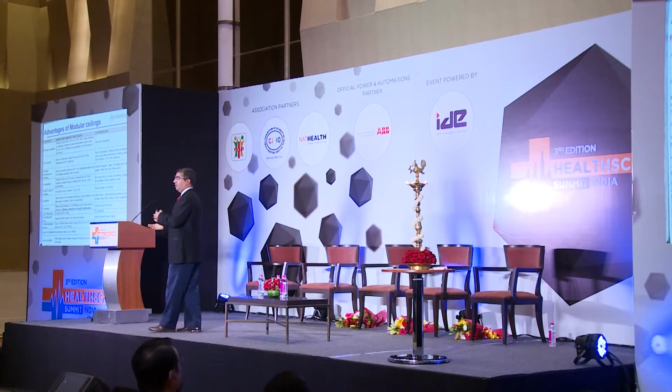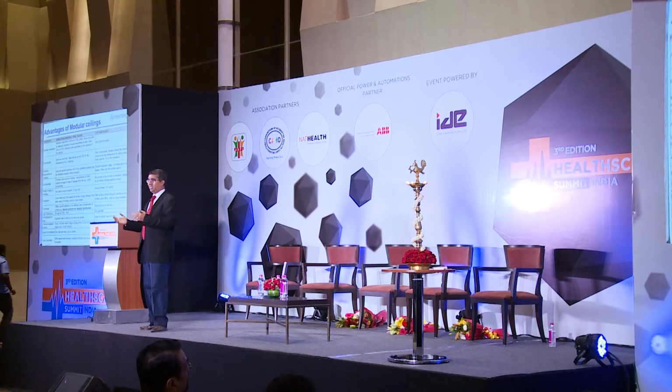And when you go for metal perforation, which is a very fatal error in most hospitals, currently also happening in India, the perforations collect dust and dirt, and if you have fleece on the backside, it becomes a backyard of bacteria and germ growth. And if a highly infectious patient comes in, that room is a fatal room for the next patient. In a way, if you don't use a different AHU where you're using perforated metal, your hospital is far more infection prone than infection control. One simple item, like I said, can make such a huge difference in the quality of air and bacteria and germ growth in your healthcare facility.